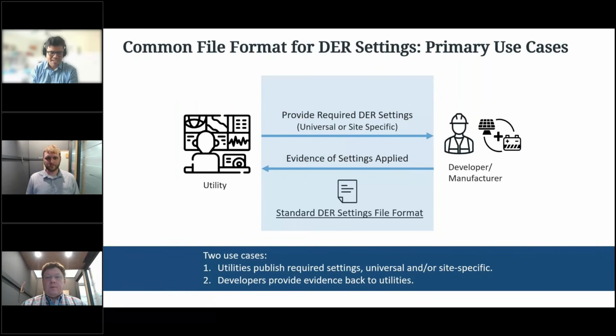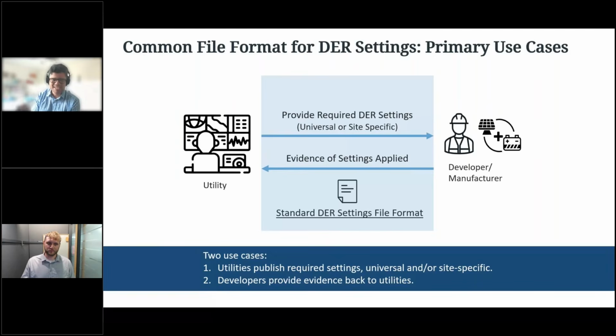The challenge we've had in the industry is that when exchanging these settings, there was no standardized file format that parties were using. For example, when utilities need to express how the DER should be set up to be allowed to interconnect to their grid, they publish their required settings. If there are 100 utilities, they're publishing that in 100 different ways, making it hard for installers to understand each one, since there are 100 different types of documents they need to understand to program the DER correctly according to what was required.